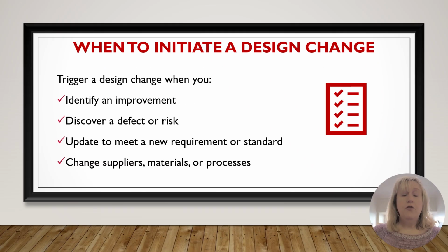So when do you initiate a design change? Whenever a change could impact form, fit, or function. This includes fixes, upgrades, or changes driven by risk management, supplier updates, or regulatory shifts. If you find yourself saying, it's just a small tweak, that's usually a good sign it needs to go through design change.